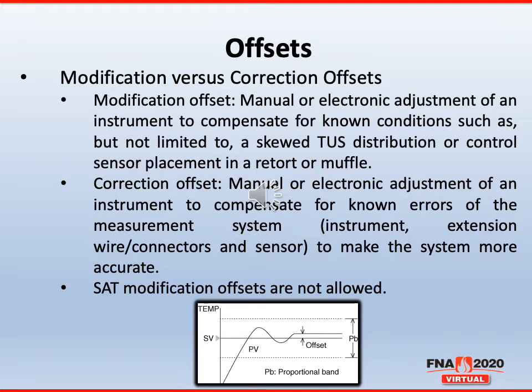So a modification offset is a manual or electronic adjustment of an instrument to compensate for known conditions such as, but not limited to, a skewed uniformity survey distribution or the control sensor placement in a muffle or retort type of furnace. So in other words, you're taking the nominal temperature and shifting it away from nominal.